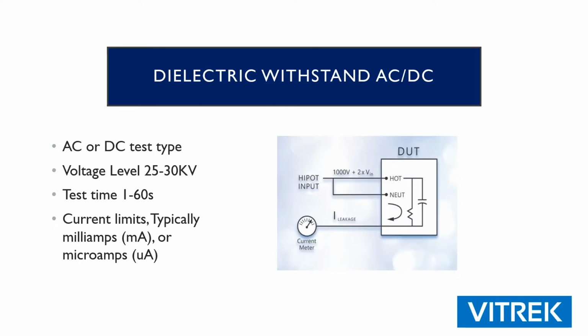All right, so we talked about it a little bit. This here is kind of a diagram showing that we're going to put high voltage on line and neutral, and then we're going to test that isolation barrier to ground for the chassis. Typically, it's 2 times the mains voltage plus 1,000. Test times can be anywhere from sub 1 second to 60 seconds or more.